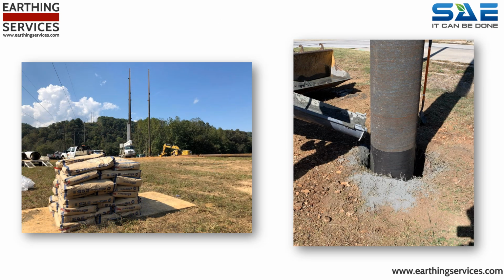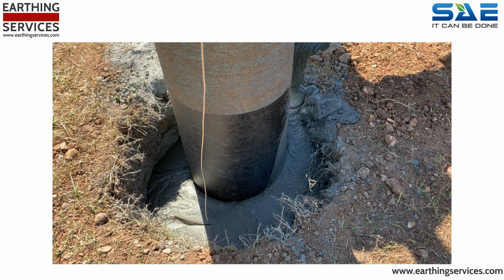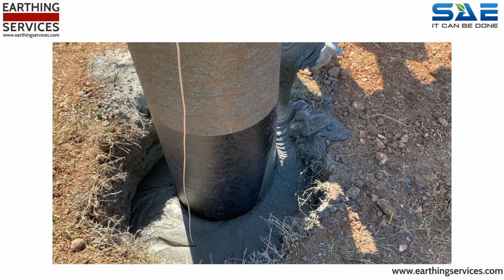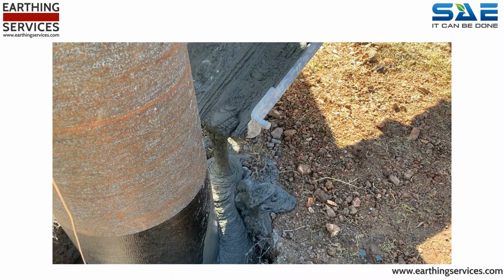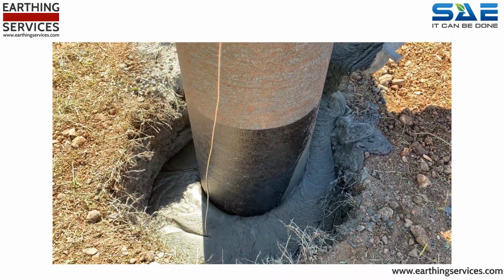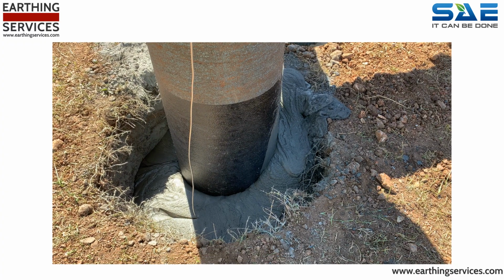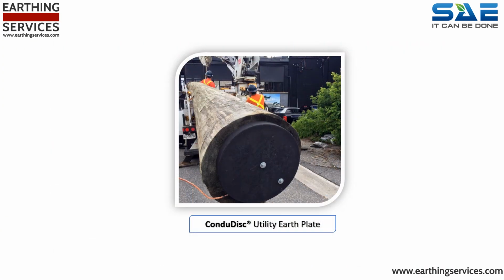Our approach is different. Instead of insulating the steel from earth, encase it in a material which will safely discharge and protect the steel from deterioration. Pour in mixed concrete. Once cured, this will provide a safe electrical earth, preventing corrosion and ensuring stability. The ConduDisc is a carbonaceous polymer with an equivalent contact surface area of a 3-meter earth rod and fault tested to 55,000 amps.